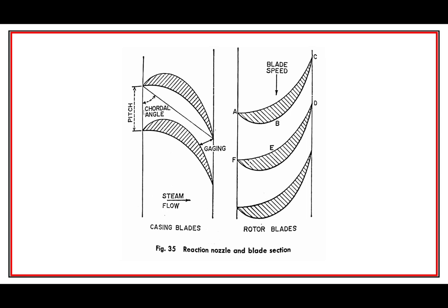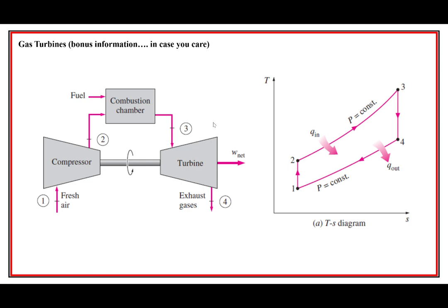Here are some reaction nozzles showing the blades up close. This is where we make velocity triangles, which are really important for planning out blade angles. The angles are related to relative velocity — the optimum angle depends on the speed the turbine is designed for. That might not be the fastest speed but somewhere in the upper-middle range, so that when the flow reaches the rotor blades it is tangent to the arc of motion.